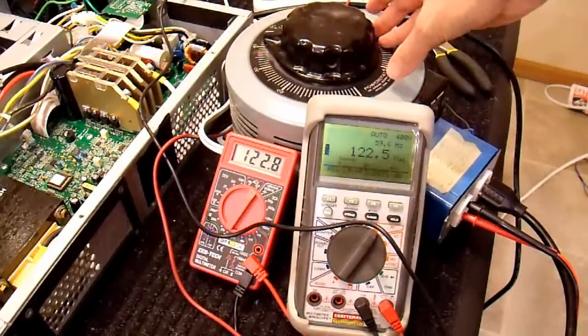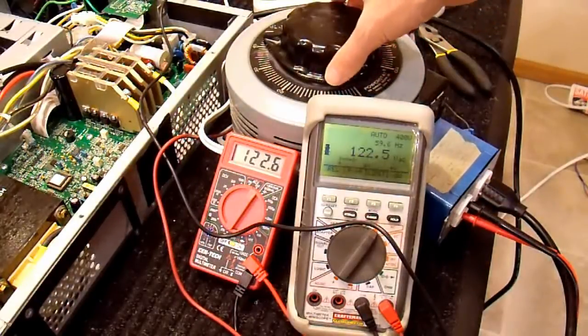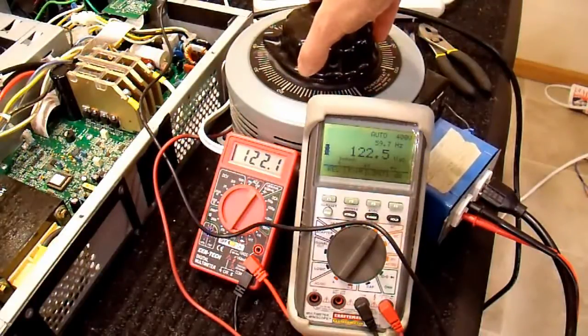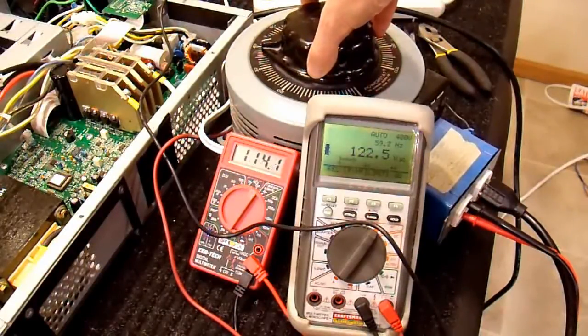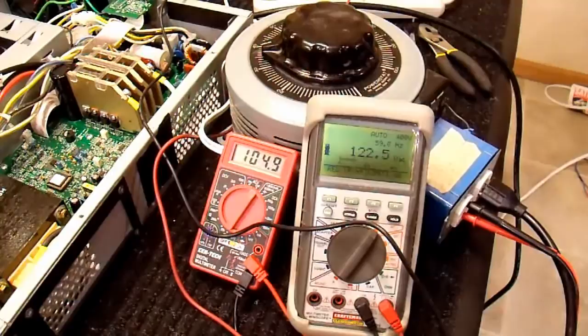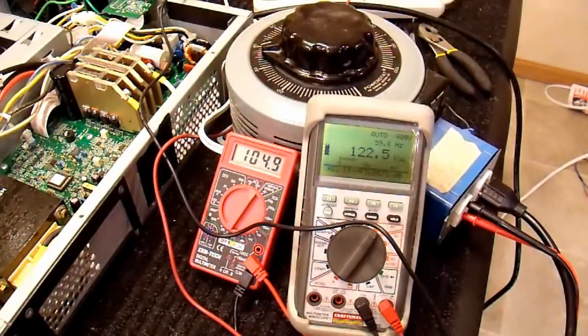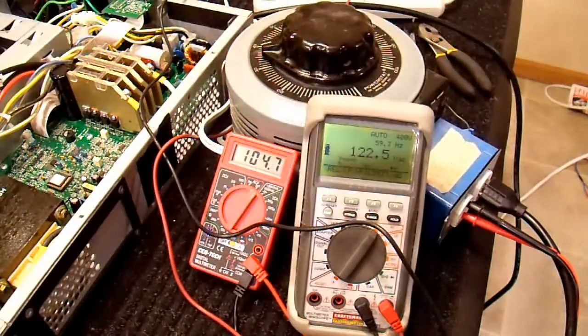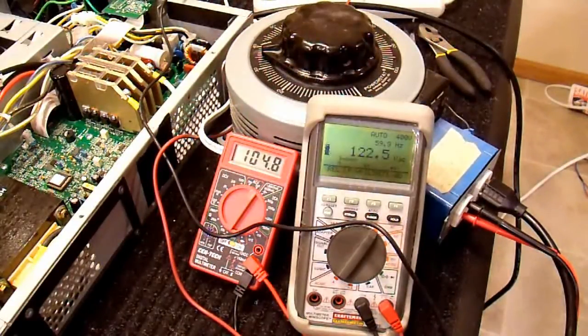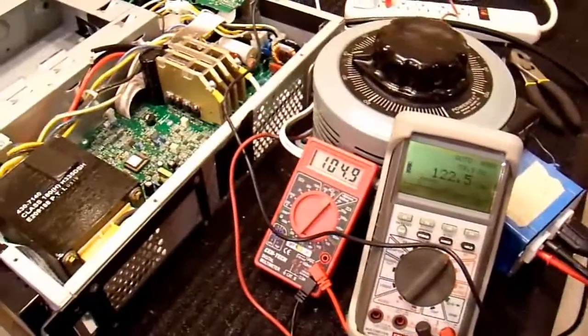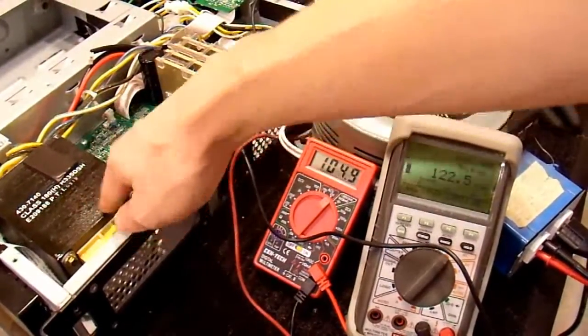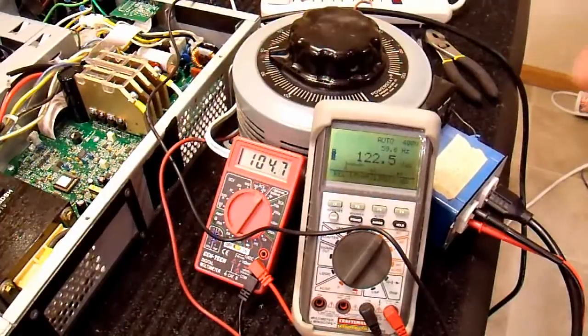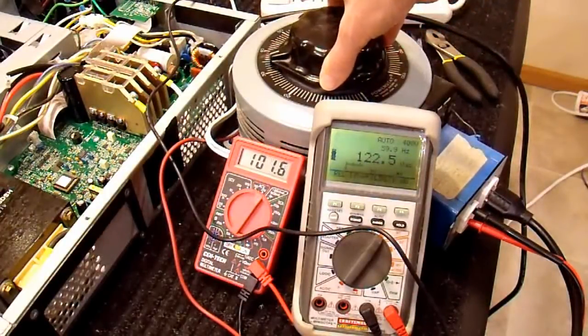So I demonstrated this earlier in an older video, my back UPS video, but if I turn this down far enough, it will click. And it just switched to a different tap on the transformer. 105 volts is what's going into the UPS. The UPS thinks that's too low, so it's switching to a different tap on this transformer to boost the voltage up to back up to around 120 volts. Turn it down again, it'll switch to another tap.